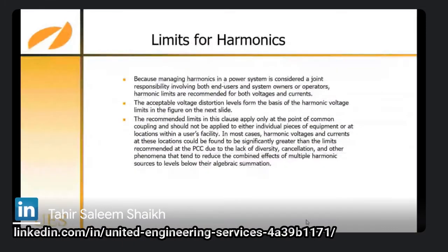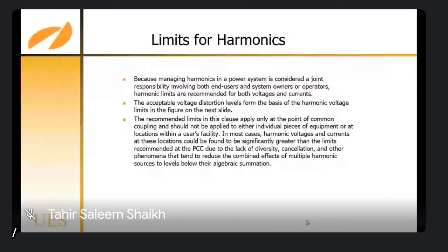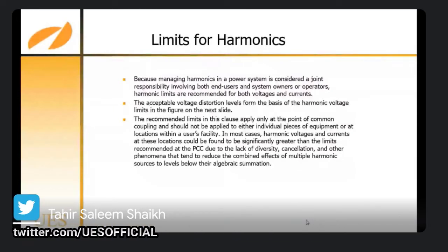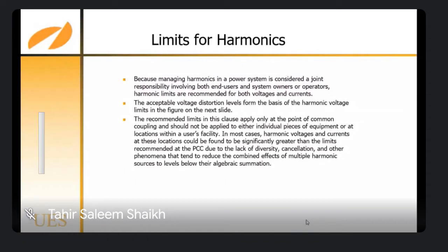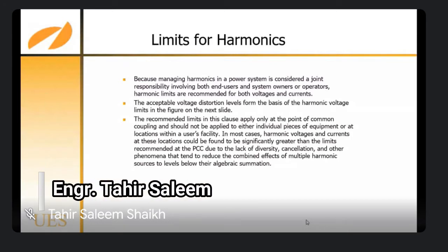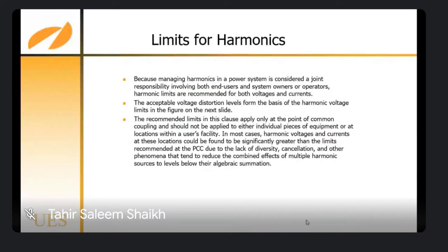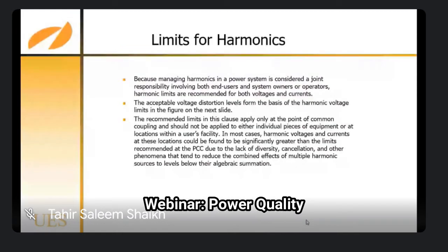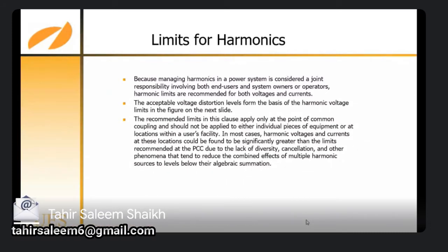Now, we come to the limits of the harmonics. What does the standard tell us about that? What should be the limits and what are the remedial measures for that, we will discuss over here. Because managing harmonics in a power system is considered a joint responsibility involving both users and system owners and operators. Harmonic limits are recommended for both voltage and currents.